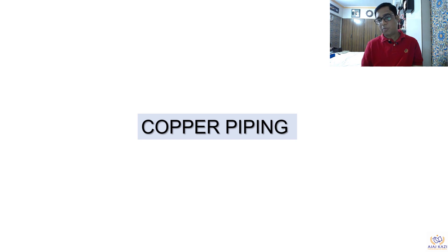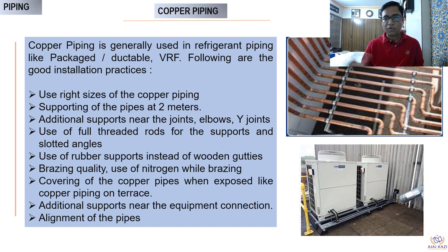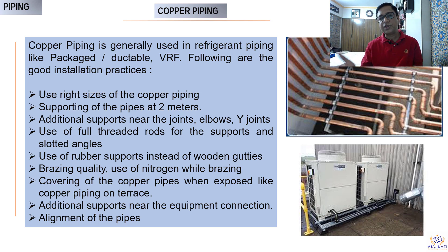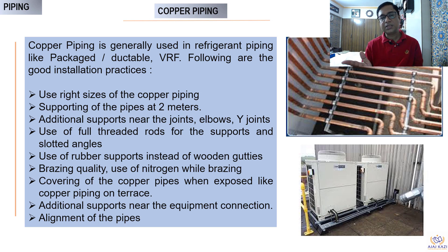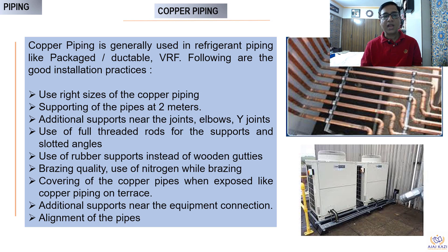Another element of piping is copper piping, generally used for DX systems and VRF systems. Looking at site photographs, we must use the right size for copper piping. Support distance varies for copper piping; while stress analysis is less critical here, supports must be provided adequately at joints and direction changes. Use rubber supports instead of wooden gatties — wooden gatties get eroded, damaged, and displaced. Rubber is the preferred material. Brazing quality is important, and using nitrogen while brazing is a key requirement for copper piping, along with proper supporting.